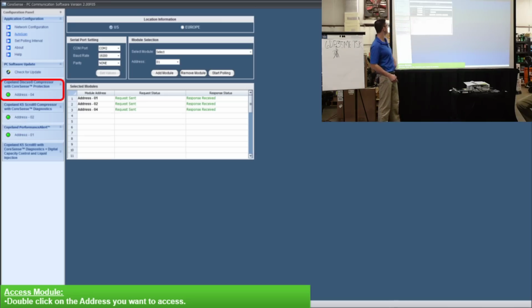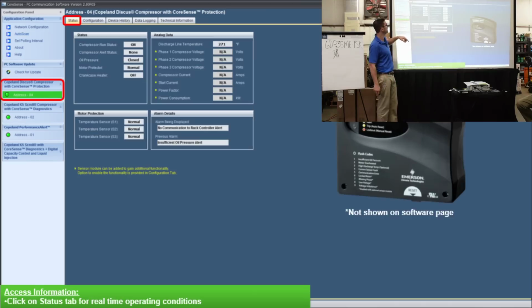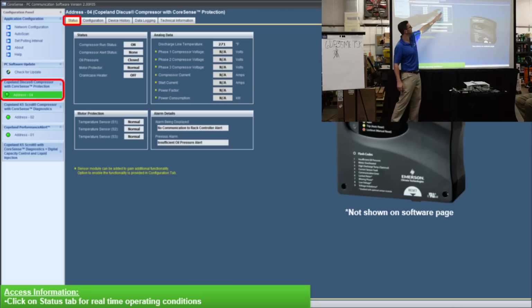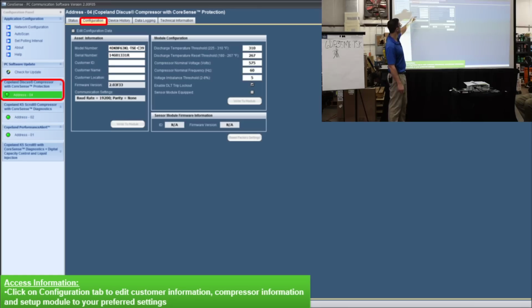So you click on one of them. We're going to click on the CoreSense protection. And this is the information you have. So if it's running, if you got alert status, if the motor protector's tripped, right? And then the sensor's inside. Then it tells you the discharge line temperature here. Okay? Then we go in. You can change the model number or the serial number if you need to. And these are all matched. So if you ever come up to a compressor and you see the serial number is different, that means that compressor is what? It's been replaced.